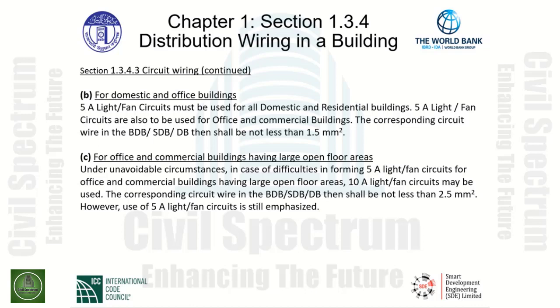The corresponding circuit wire in the BDB, SDB, and DB then shall be not less than 2.5 square millimeters. However, use of a 5-amp light fan circuit or circuits is still emphasized.